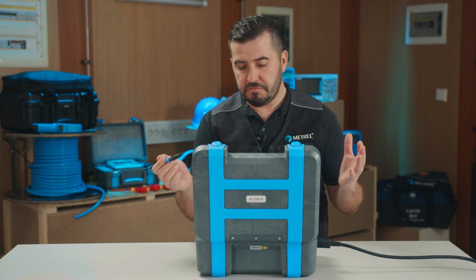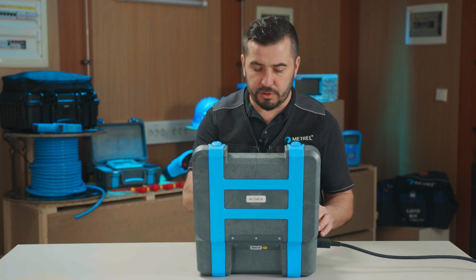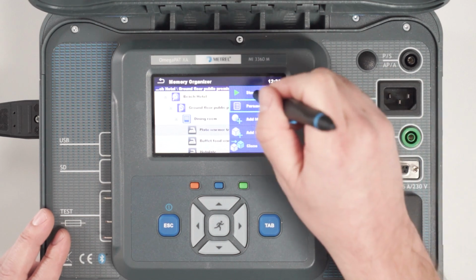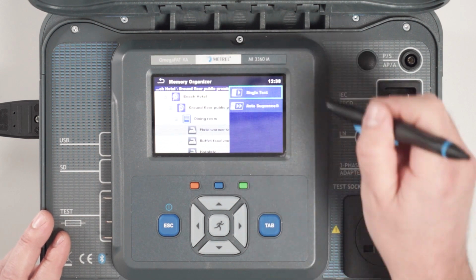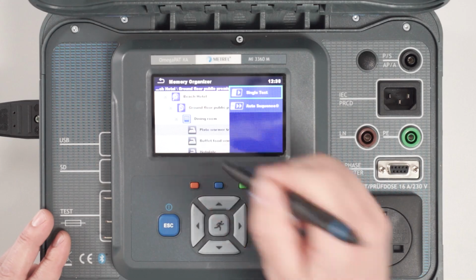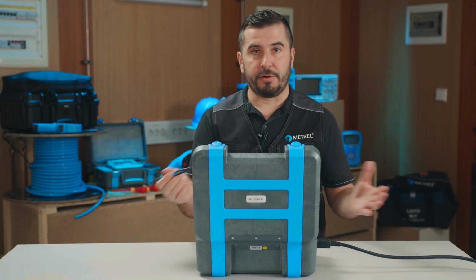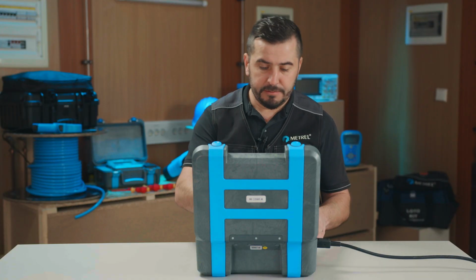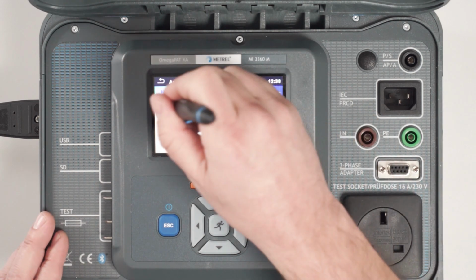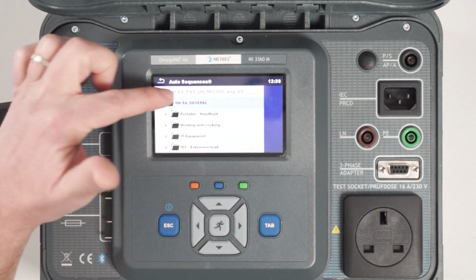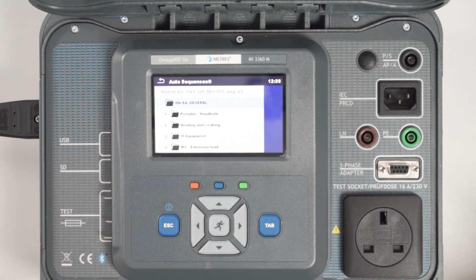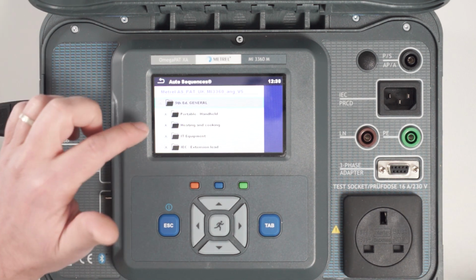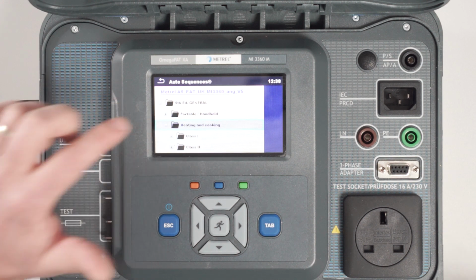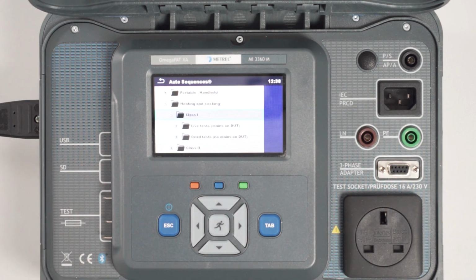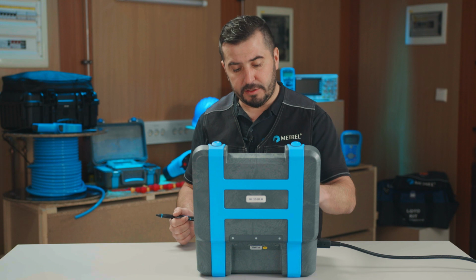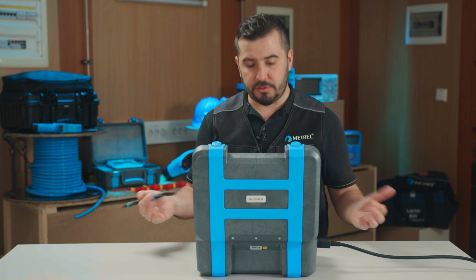So for example, if we are testing a general portable appliance, we can go here under Start Test and select we would like to start an auto sequence for, I don't know, for a kettle. We go in the auto sequence and we say, okay, we will use one auto sequence from the 5th edition general group of auto sequences. This will be heating and cooking class 1 appliance with live tests, and this means that it will be connected to mains.